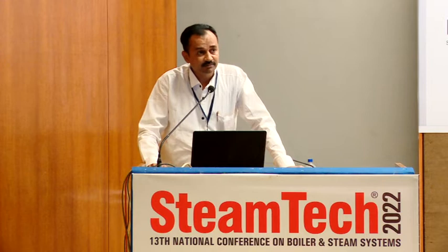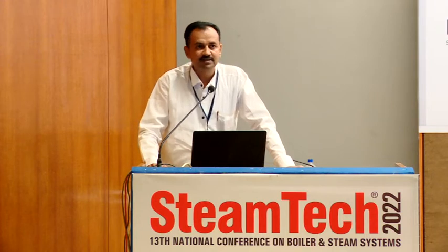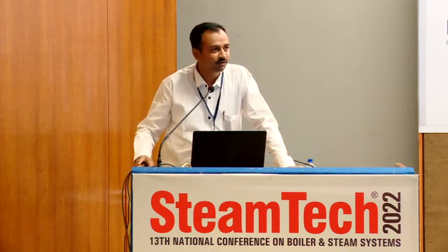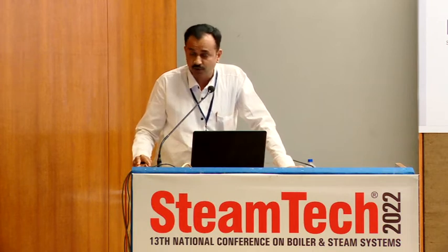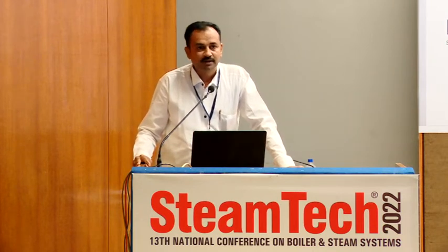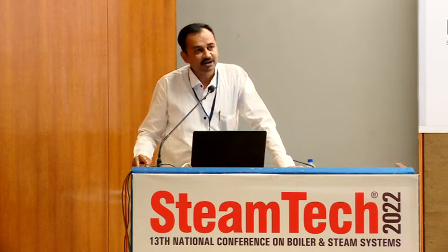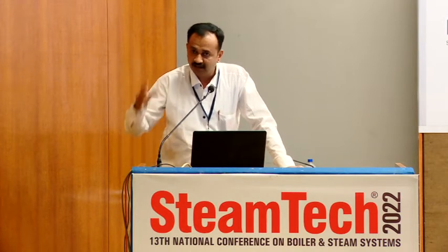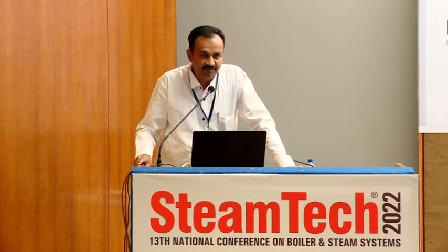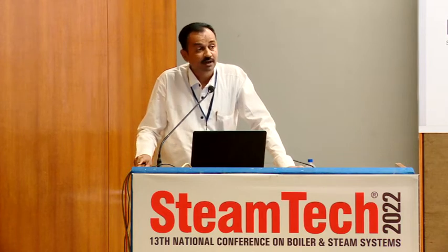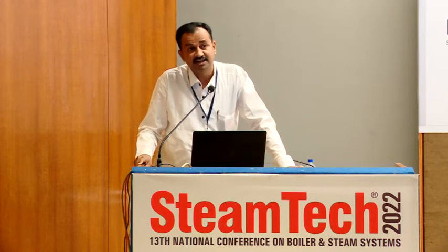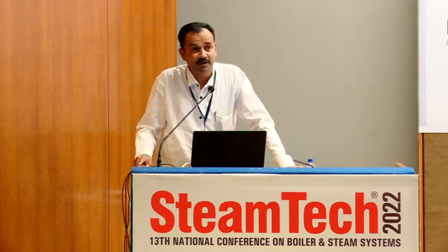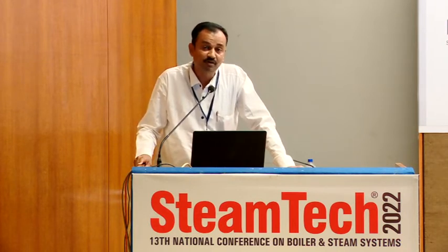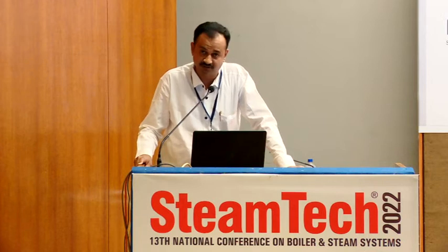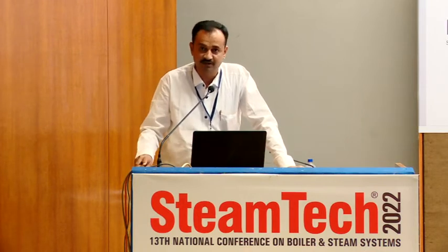So when he installs the boiler, he is keeping in mind that my boiler will always give the rated efficiency, but it's not true. The boiler gives the actual efficiency, which might not be the rated efficiency. And from the audit reports and from the survey we conducted in the boiler house, we came to know that this efficiency is derated to the tune of at least 15 to 20%, and sometimes 40% for the manual fed boiler also. So there is a huge opportunity for that.